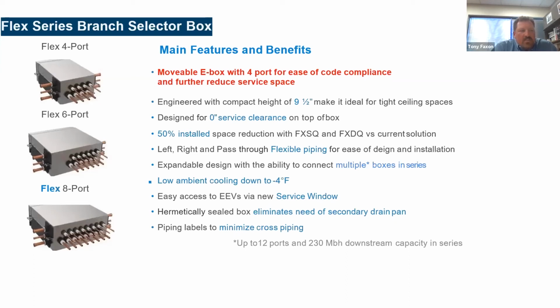Now, one of the reasons VRF has been so popular around the world over the last 38 years is how little space it takes up when compared to other systems. So the first notable difference in this new revision is the reduction in both height and in required ceiling space. The previous BS boxes were quite small as they were, just under 12 inches, but it's important to note that they always required 4 inches of open space above and below the installation. So you needed a 20-inch cavity. Now with newer fan coils that only require about 9 inches or 12 inches of ceiling space, that 20-inch cavity was becoming an issue. So the new multi-port boxes are only 9.5 inches tall, and they have a 0 clearance for service, which is a significant space savings.